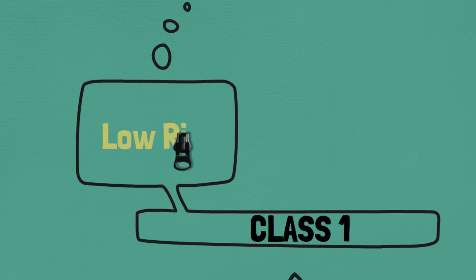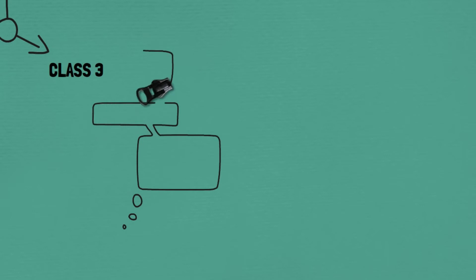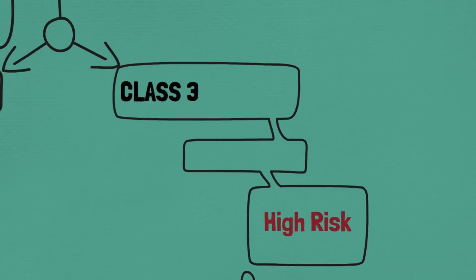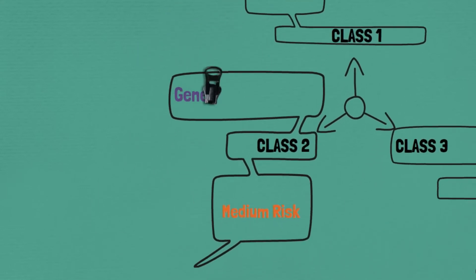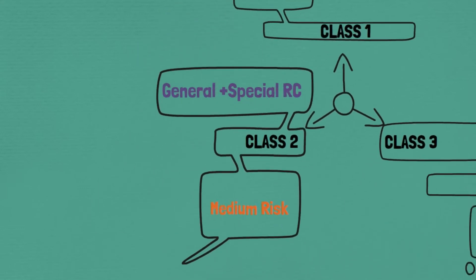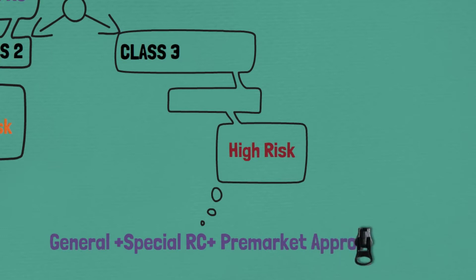According to the FDA classification, Class 1 devices are low risk devices, Class 2 devices are medium risk devices, and Class 3 devices are high risk devices. Class 1 devices require general regulatory control, Class 2 devices require general plus special regulatory control, and Class 3 devices require general plus special regulatory control and pre-market approval. Special regulatory control includes special labeling requirements, mandatory performance standards, and post-market surveillance. Pre-market approval is the FDA process of scientific and regulatory review to evaluate the safety and effectiveness of Class 3 devices.